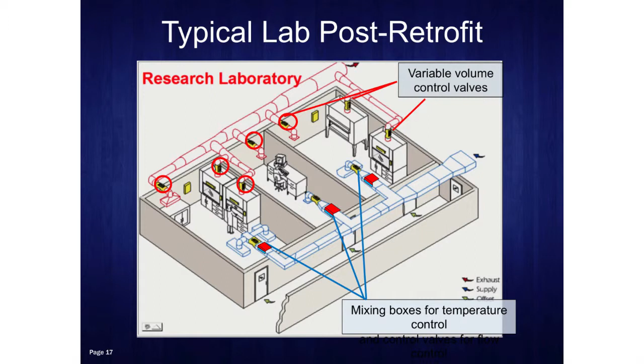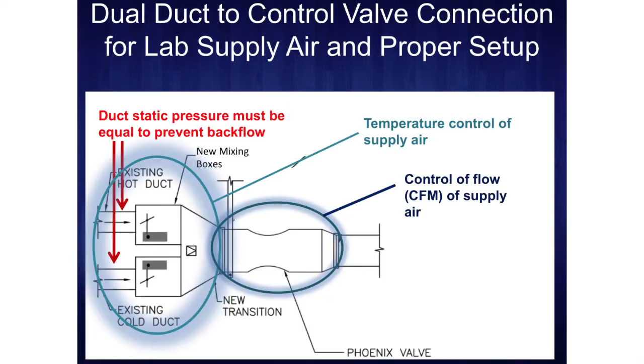whichever you choose, you have a few things to look out for. And this is all in the prerequisites, right? So static pressure must be equal. If you do not set the static pressure on the hot and cold decks equal, you will backfeed one into the other, and you will have a very difficult time making temperature. So these are kind of the lessons learned, right? It is possible to retrofit these buildings. It's possible to do it without ripping out everything and going to terminal reheat. But you have to understand that there are challenges within the system.